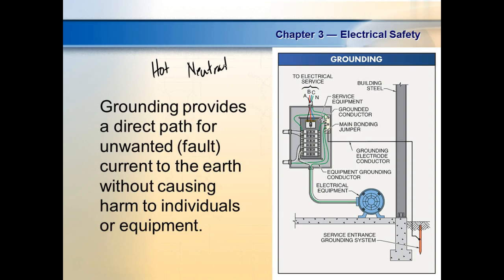Of course, we have what we call double insulated tools, and these are the tools where the cases are plastic. So the cases are plastic, which means you don't have to have a ground. A lot of times the plugs are polarized. You ever notice the 120 volt plug? It's got blades on it. Have you ever noticed something? One of them's bigger than the other one. Does that mean anything? This is supposed to be the neutral. And then this is supposed to be what they call hot. So a lot of times they use a polarized plug. They just want to make sure you plug it in correctly. So grounding provides a direct path for unwanted fault current to earth ground without causing harm to the individual and equipment.